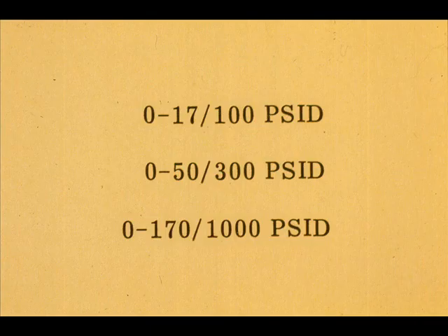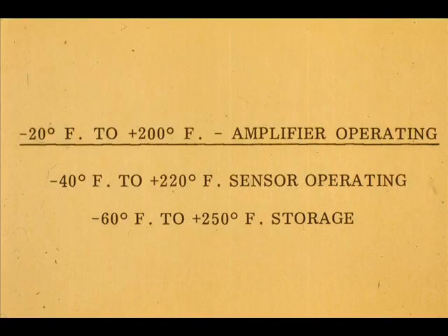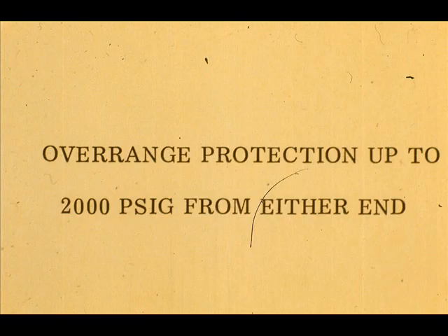The Rosemount high differential pressure transmitter is suitable for measuring the PSI differentials shown on this table. The operating temperature limits on the sensing element are −40 to 220°F; oversteam tracing or overheating by any means will destroy the silicon oil-filled sensor module. The amplifier operating temperature limits are −20 to 200°F. The transmitter will withstand an overrange up to 2,000 PSIG without damage, but it is good practice to recheck calibration after any severe overrange.